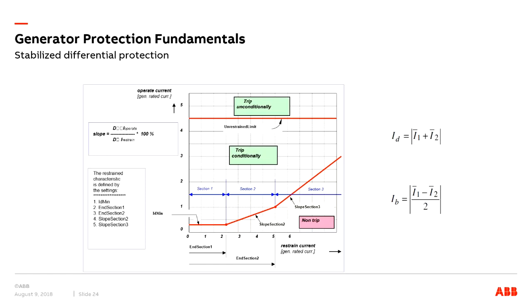Whereas in section 2, a minor slope is introduced, which is supposed to cope with the false differential currents proportional to higher than normal currents through the current transformers. And when we move to section 3, we have a much higher slope, and it is designed to result in a higher tolerance to substantial current transformer saturation at high through-fault currents, which may be expected in this section. So having a multi-slope characteristic helps the stability of the protection.